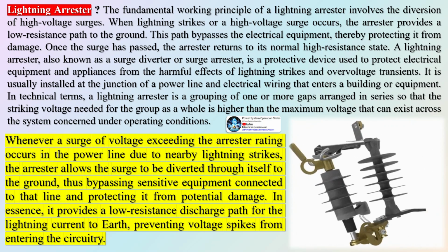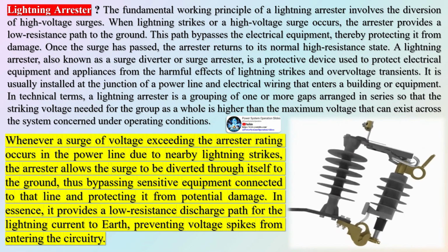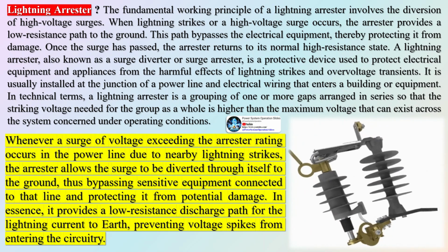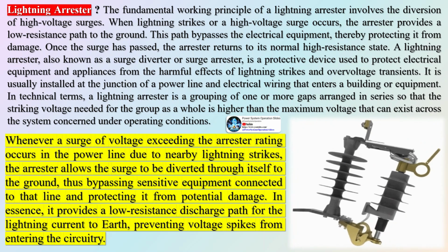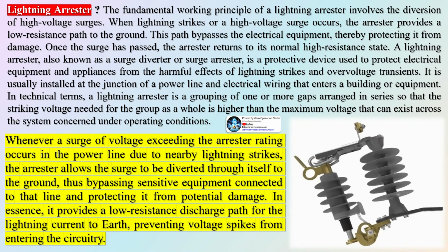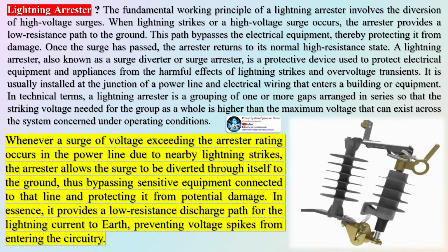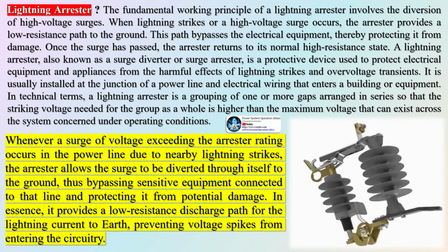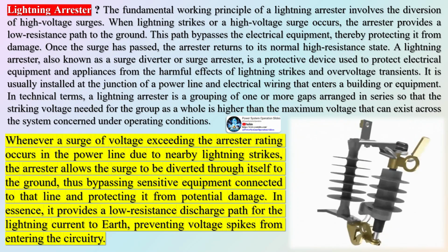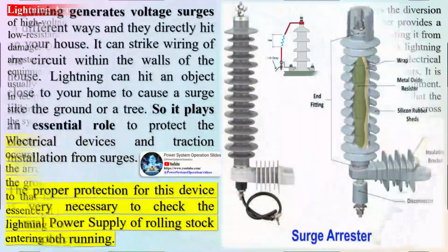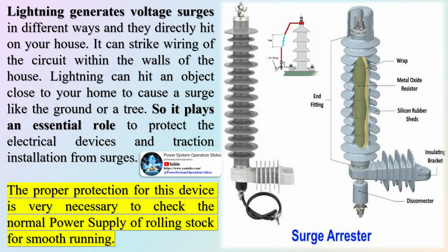A lightning arrestor, also known as a surge diverter or surge arrestor, is a protective device used to protect electrical equipment and appliances from the harmful effects of lightning strikes and overvoltage transients. It is usually installed at the junction of a power line and electrical wiring that enters a building or equipment. In technical terms, a lightning arrestor is a grouping of one or more gaps arranged in series so that the striking voltage needed for the group as a whole is higher than the maximum voltage that can exist across the system concerned under operating conditions.